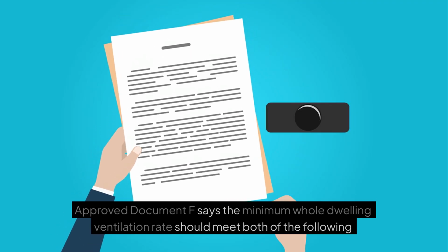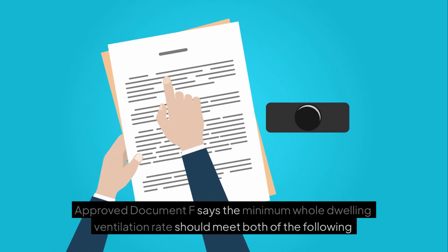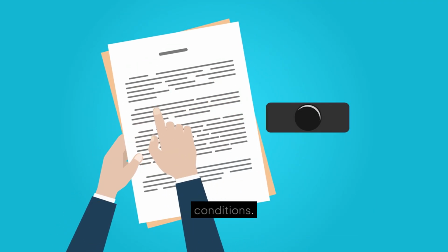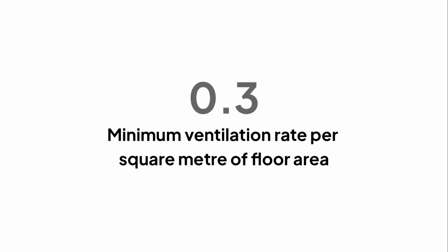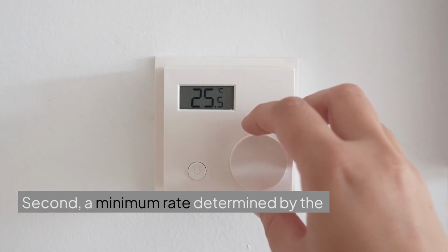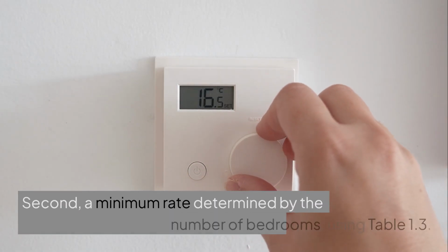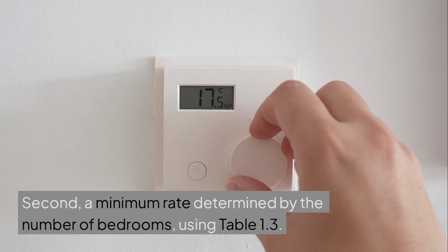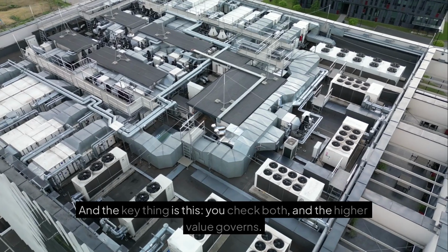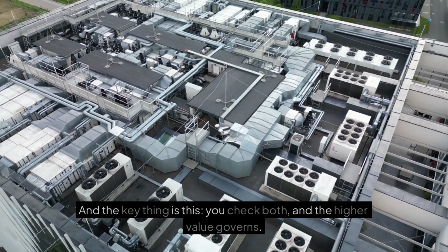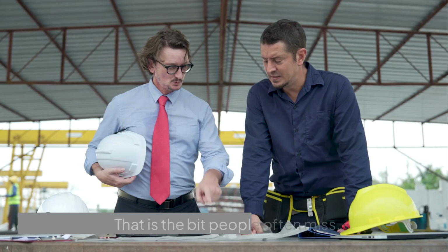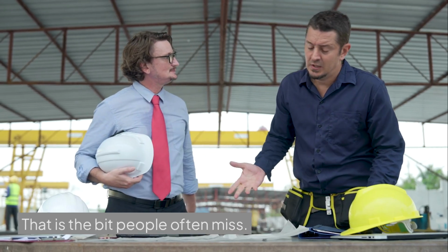Approved Document F says the minimum whole dwelling ventilation rate should meet both of the following conditions. First, a minimum rate of 0.3 litres per second per square metre of internal floor area. Second, a minimum rate determined by the number of bedrooms, using Table 1.3. And the key thing is this, you check both, and the higher value governs. That is the bit people often miss.